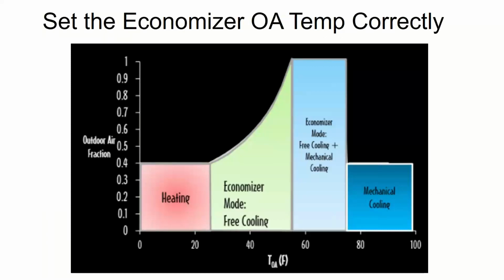Most of these systems have economizers, which we'll discuss in detail next Friday. But if you didn't know, an economizer is an outside air damper in your equipment that lets you suck in more outside air to get free cooling. If I want to cool my building and it's 60 degrees outside, instead of turning the compressor on, let's open up the damper and bring more outside air in. 60 degrees will help cool my building pretty well.